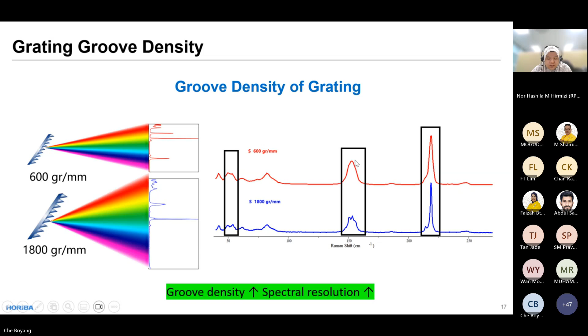There are so many optics inside the Raman microscope, so alignment is actually very important. You have to make sure all the optics are in good alignment so that your instrument is in the best condition to function. The typical way to do the alignment is that we ask our service engineer to go to the customer site and manually align the system for the customer.